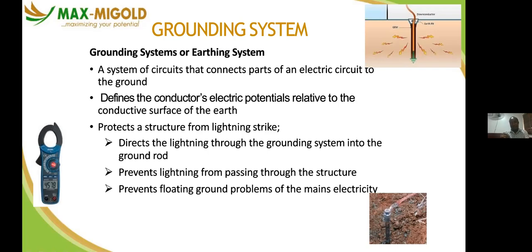And salt also, salt is your electrolyte. It helps to conduct the fault electricity or the leakage current to the ground. And the resistance of your ground must not exceed 5 ohms, 5 ohms and below. That is the value. When you are carrying out an earth test, we recommend every 6 months, but sometimes we do once a year. So the value you get must not exceed 5 ohms. If you exceed 5 ohms, that means it must be improved on. You must improve it by servicing that earth point.